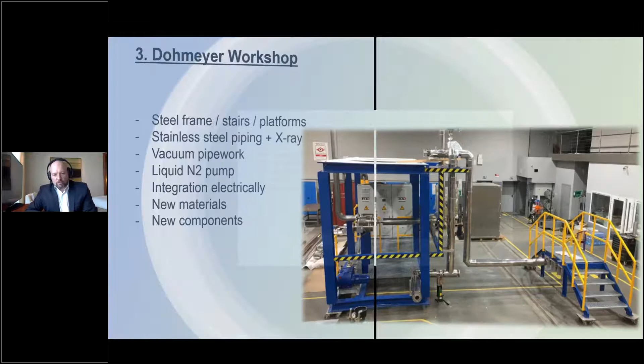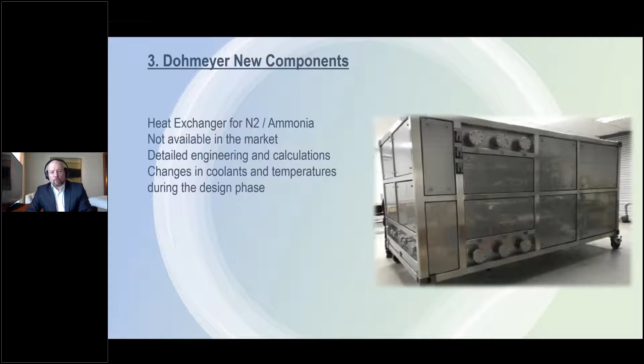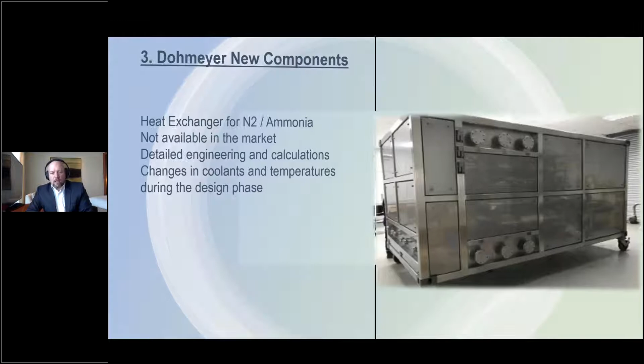Let me show you what new materials and components we have used. For example, the heat exchanger, which had to exchange the cold from the liquid nitrogen or gaseous nitrogen with the ammonia. It had never been built before, and it was a challenge to do the study and the engineering. We looked at different types of coolants, intermediate coolants, and types of heat exchanger. But this is the result: a heat exchanger where 3 streams of cold gas go in, and 3 streams of cold ammonia gas come out. Another challenging material was the recirculation fan.